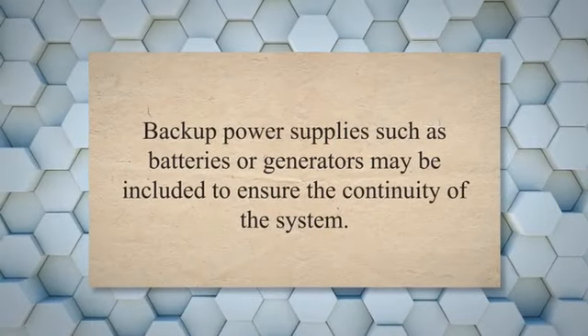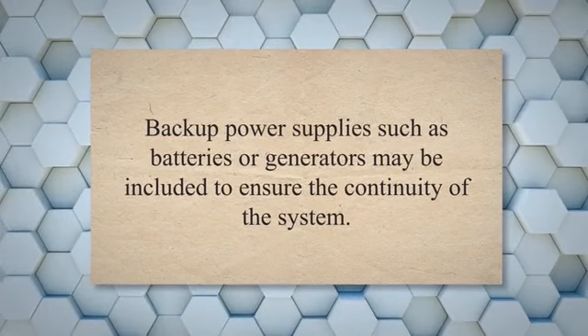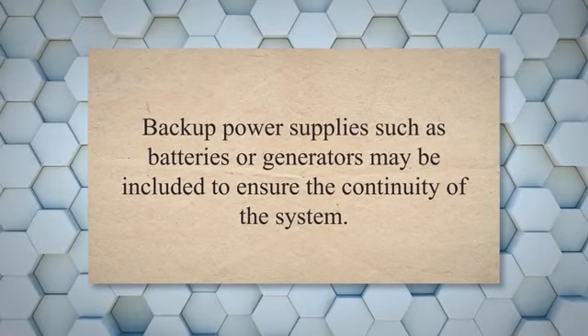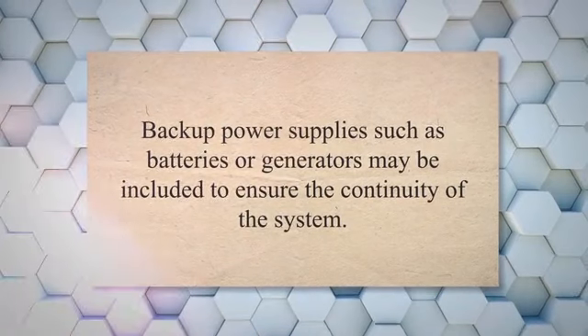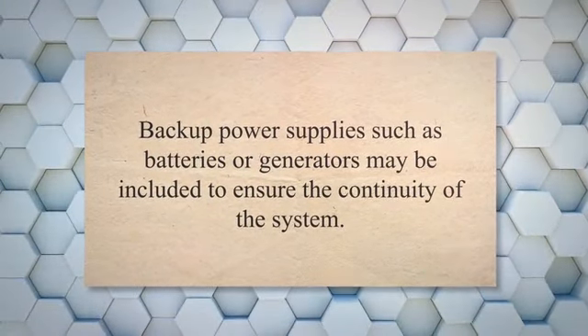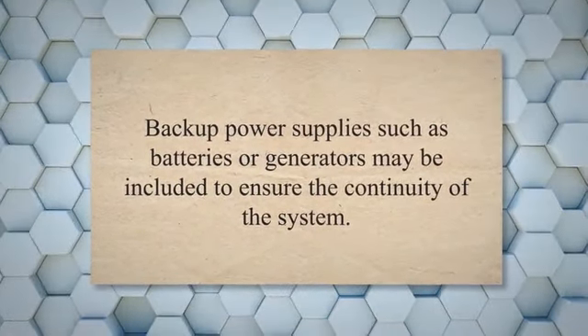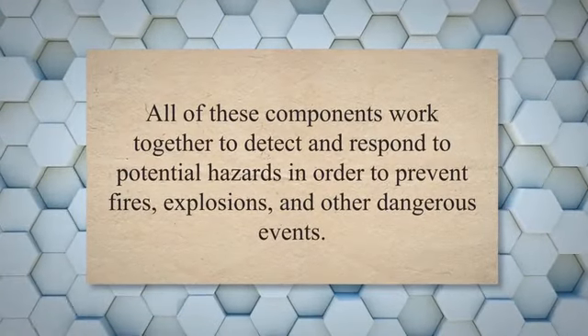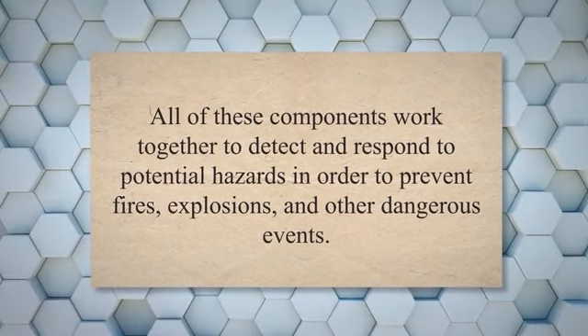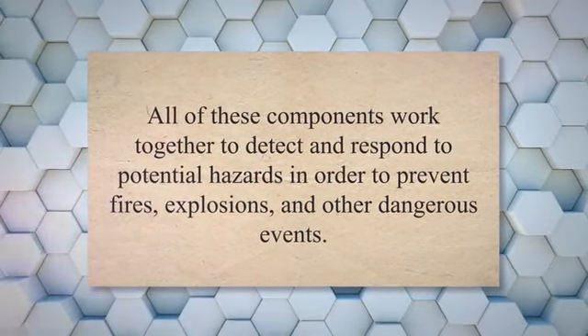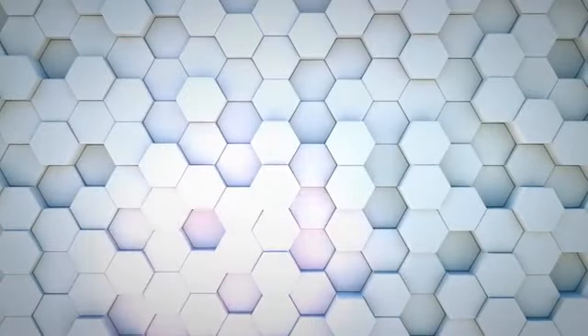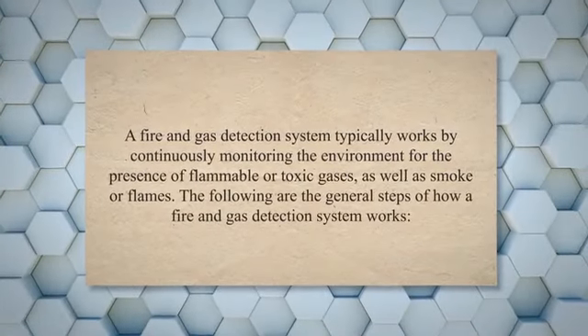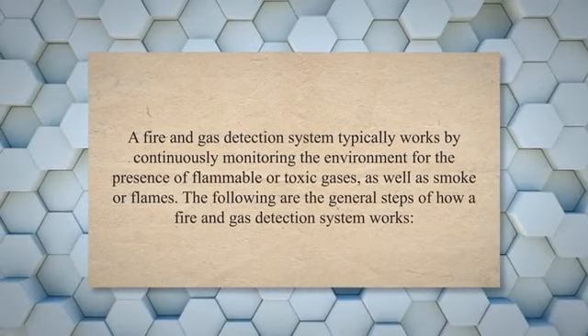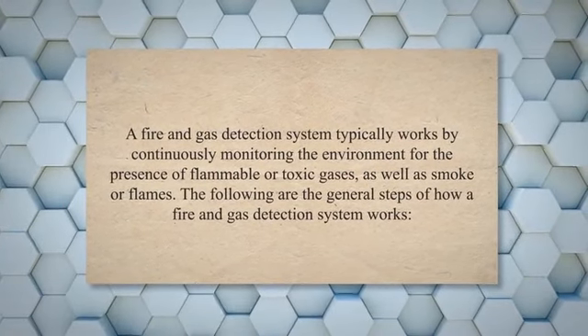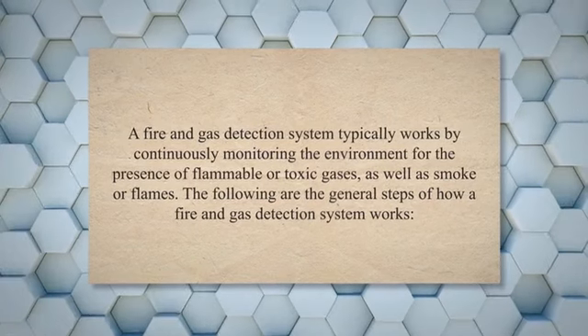Power supply. The system requires a reliable power supply to ensure that it is always operational, even during a power outage. Backup power supplies such as batteries or generators may be included to ensure the continuity of the system. All of these components work together to detect and respond to potential hazards in order to prevent fires, explosions, and other dangerous events. A fire and gas detection system typically works by continuously monitoring the environment for the presence of flammable or toxic gases, as well as smoke or flames.